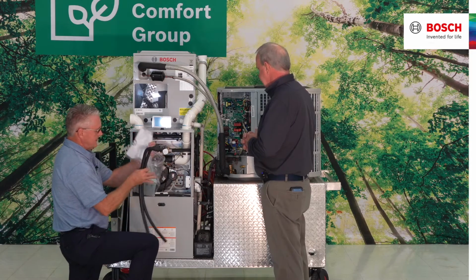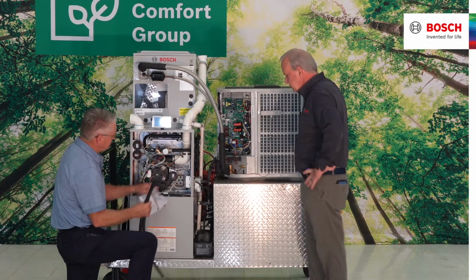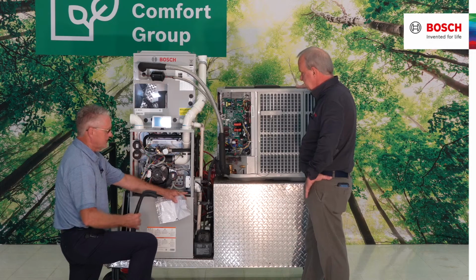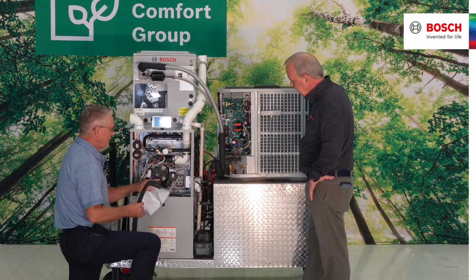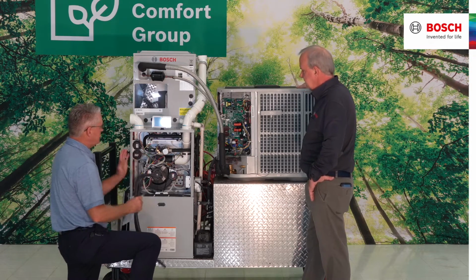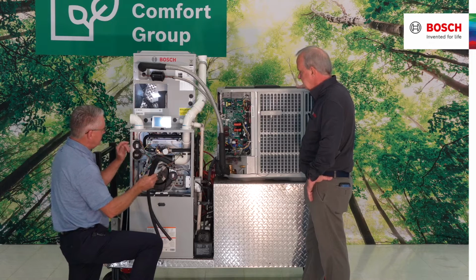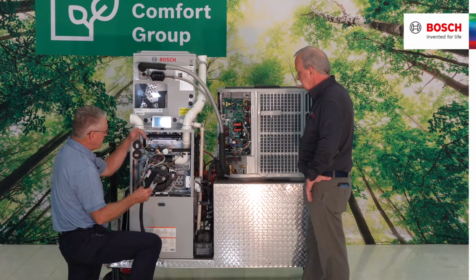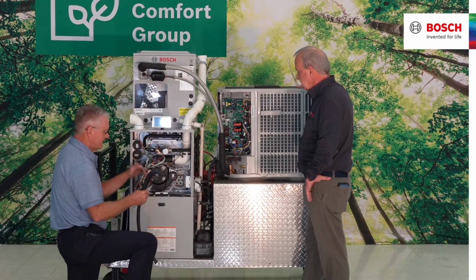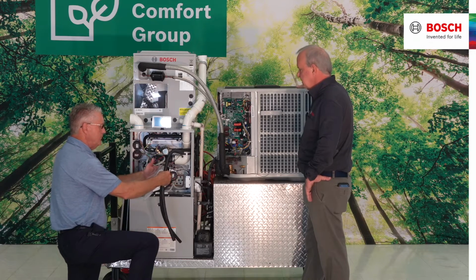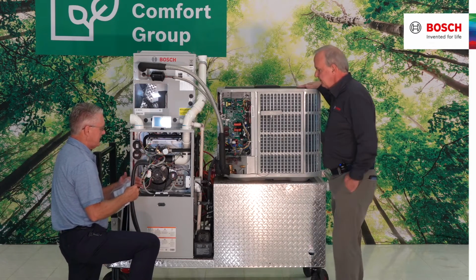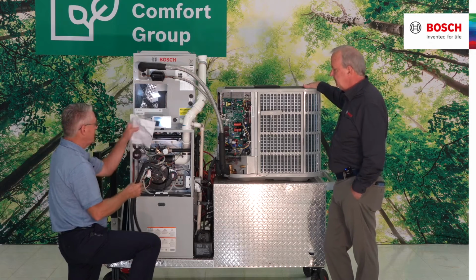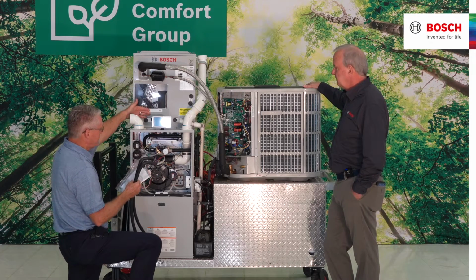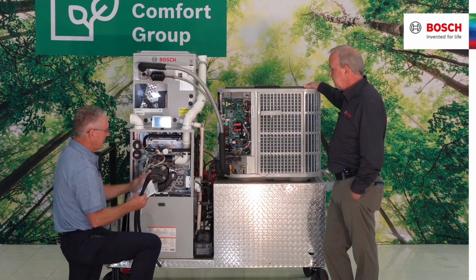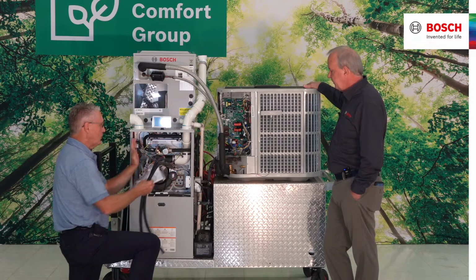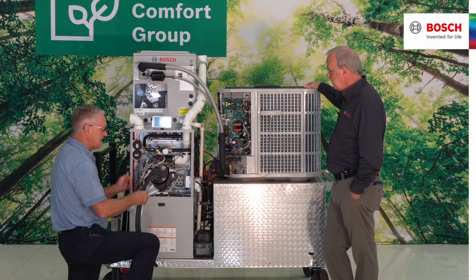So Ken, in this bag, I have hoses that go from my secondary heat exchanger down to the collection port. The reason that I have hoses is that as I run the gas through the heat exchanger and I bring it back down into that secondary heat exchanger, that's when I'm going to remove all the moisture away from that gas, producing condensation just like this evaporator would be doing in the summertime, so I have to get rid of that water. Correct. That's why this unit is called a condensating furnace.